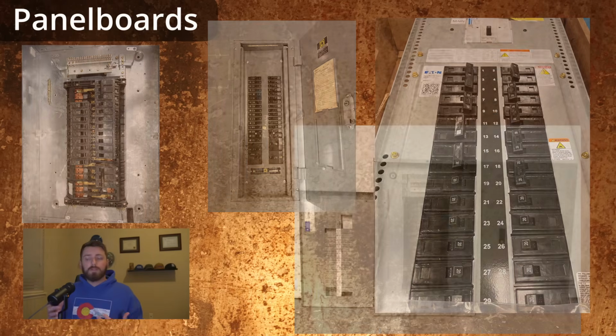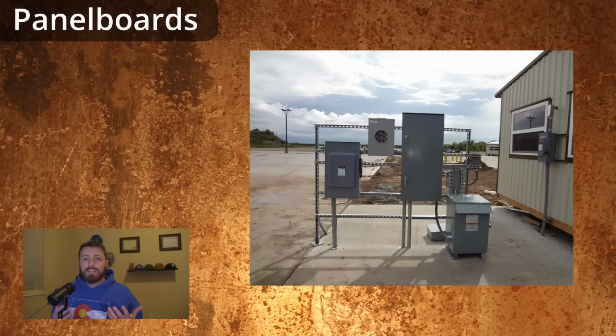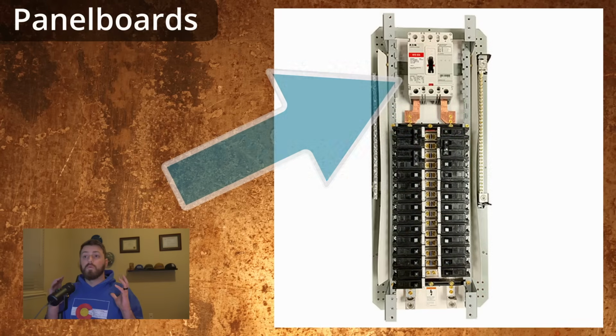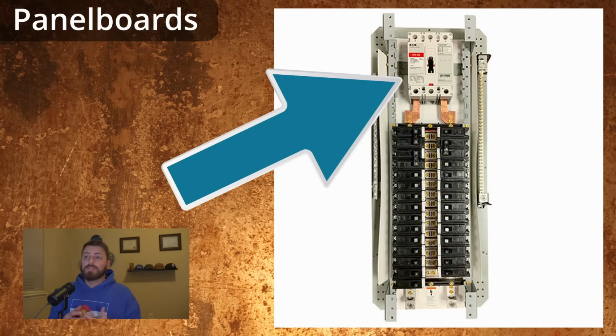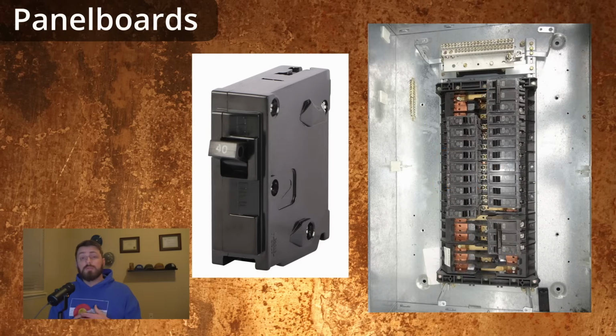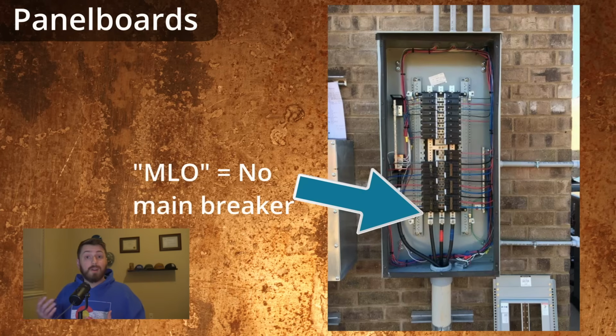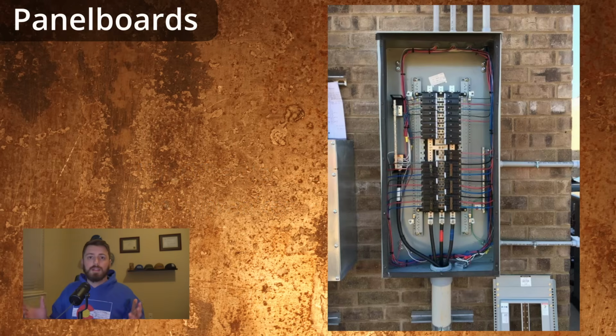Panel boards are typically wall-mounted, though in industry there are sometimes ones you'll see freestanding on pedestals or hanging from unistrut, things like that. In general, these contain one larger main breaker sized to protect the whole board and be big enough to carry all of the connected loads. There will be anywhere from a couple to a few dozen smaller MCBs, or miniature circuit breakers, feeding out to each load. Though if the protection upstream is adequate and close enough, some panel boards are what we call MLO panels, or main lug only, meaning they aren't equipped with a main breaker. The feed coming in lands directly on the main bus, and the feeder breakers protect the downstream loads by themselves.